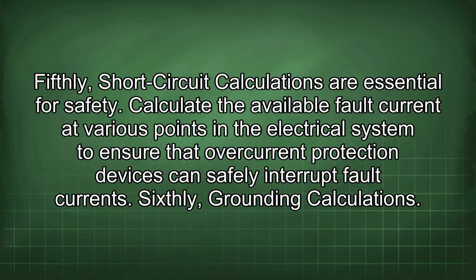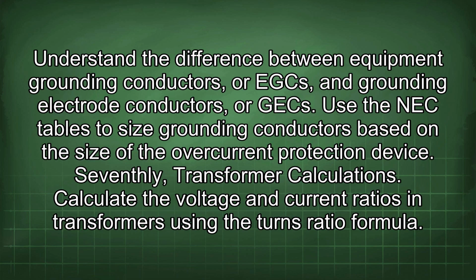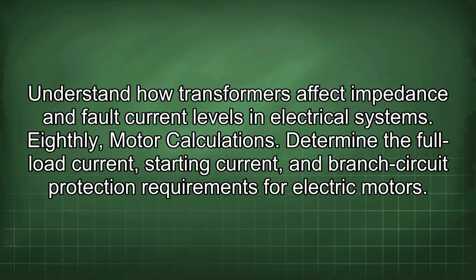Fifthly, short circuit calculations are essential for safety. Calculate the available fault current at various points in the electrical system to ensure that overcurrent protection devices can safely interrupt fault currents. Sixthly, grounding calculations. Understand the difference between equipment grounding conductors, or EGCs, and grounding electrode conductors, or GECs. Use the NEC tables to size grounding conductors based on the size of the overcurrent protection device. Seventhly, transformer calculations. Calculate the voltage and current ratios in transformers using the turns ratio formula. Understand how transformers affect impedance and fault current levels in electrical systems.